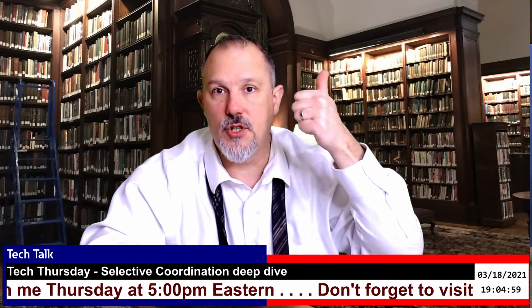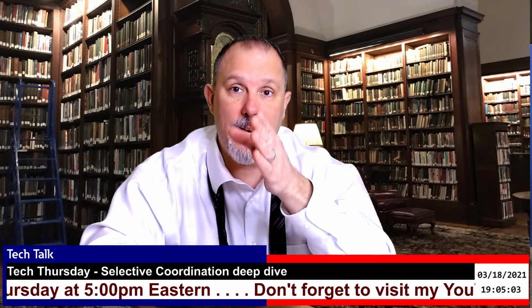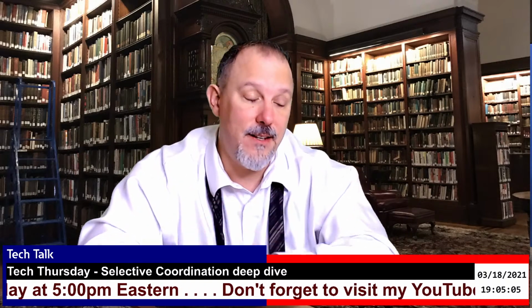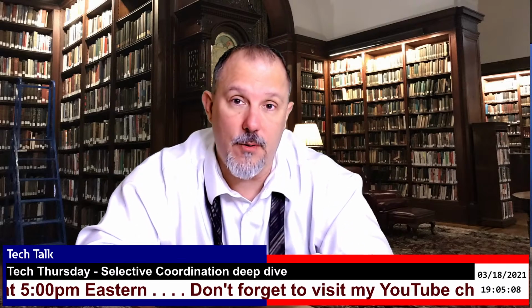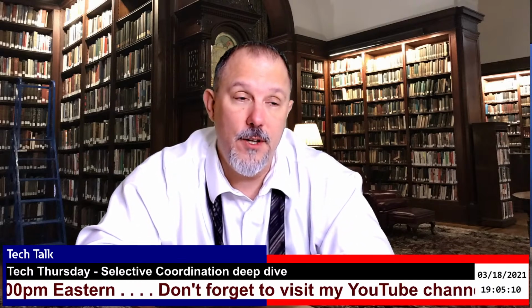Yes, you do. That is the hardest part, because think about what a ground fault current is. All the current is going to be flowing from, say, phase A to ground. The overcurrent device that's going to have to compete with the zero sequence relay or the ground fault sensor in the device upstream is going to see that current too. And if you don't coordinate at that ground fault current, then yeah, you've got to think about it.